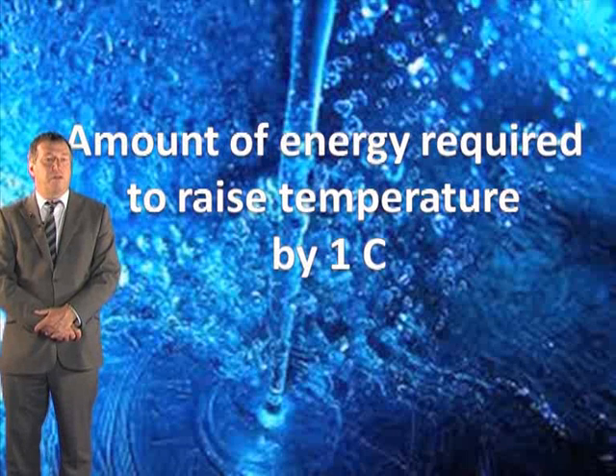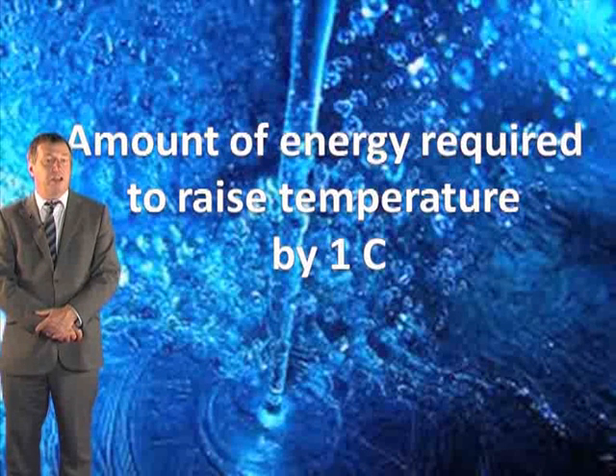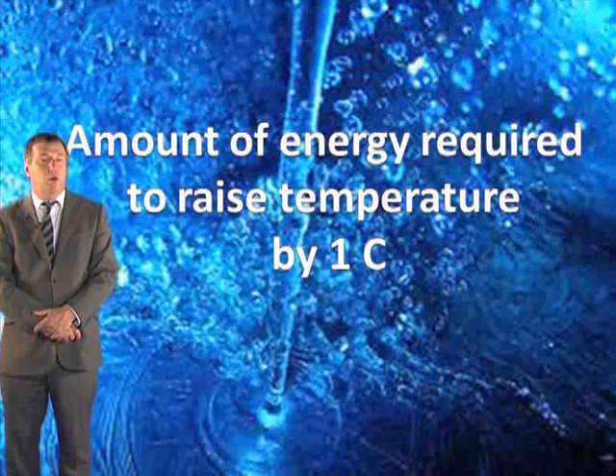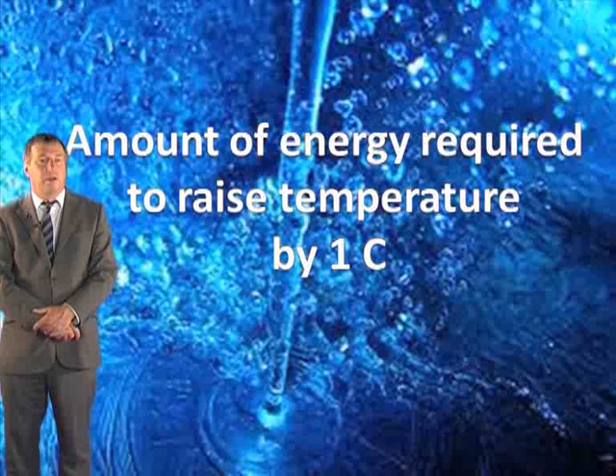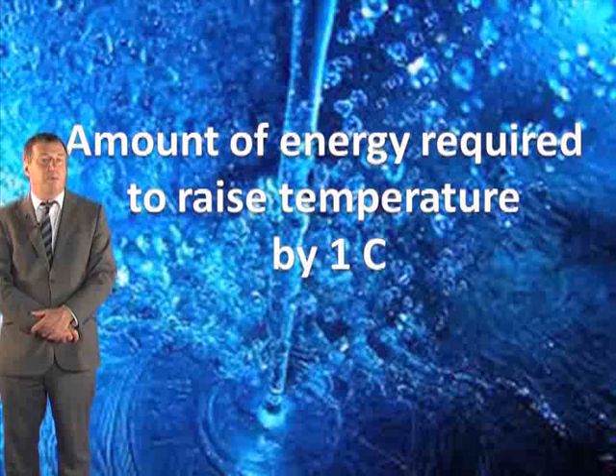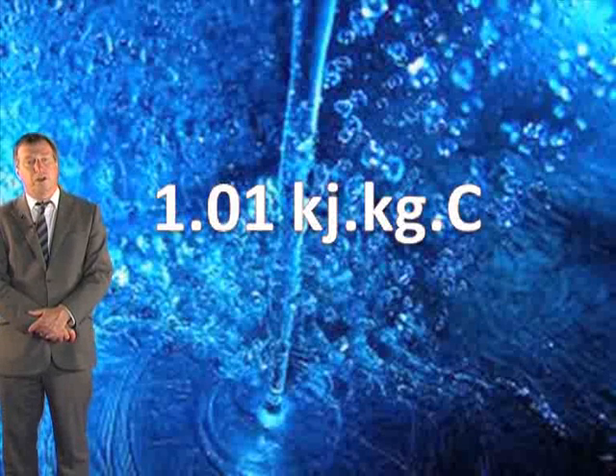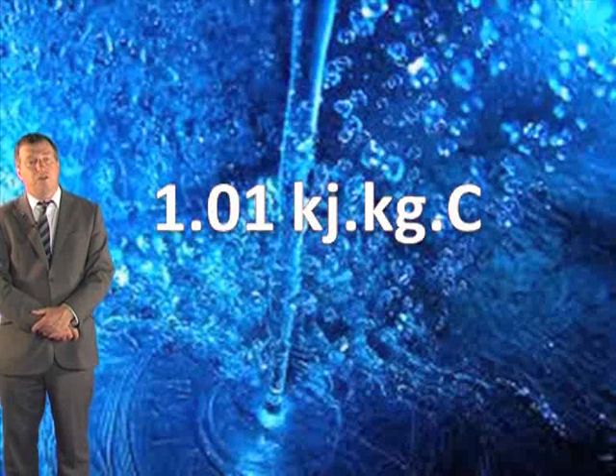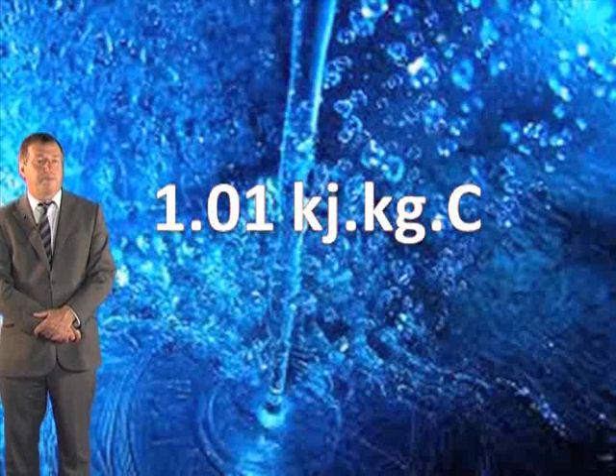Specific heat is the amount of energy, measured here in kilojoules, that is required to raise 1 kilogram of material by 1 degree C. Though the value varies slightly depending upon the temperature of the smoke, the value of 1.01 kilojoules per kilogram per degree C is suitably accurate for our purposes here.